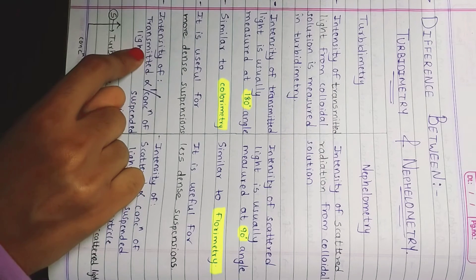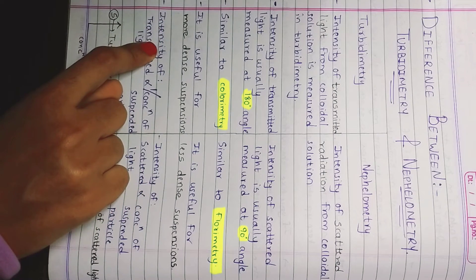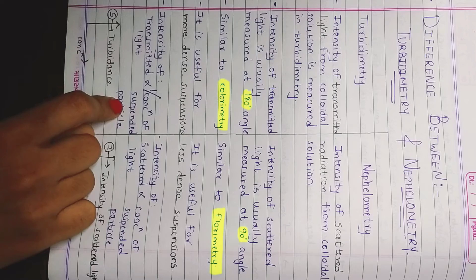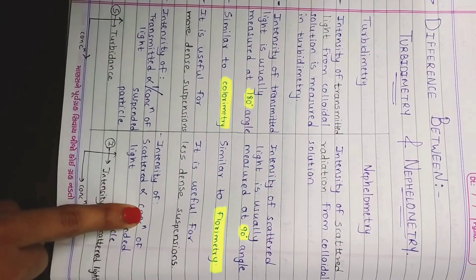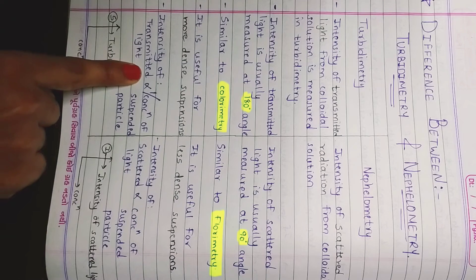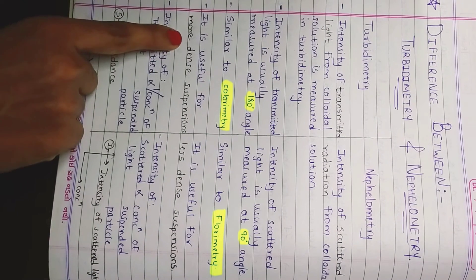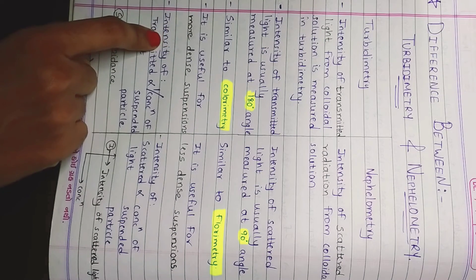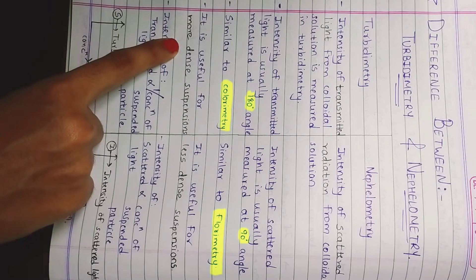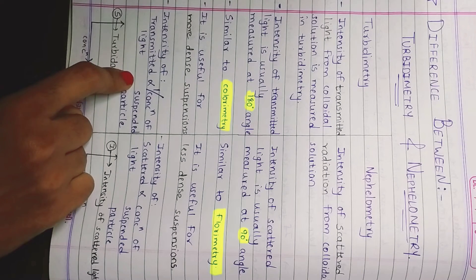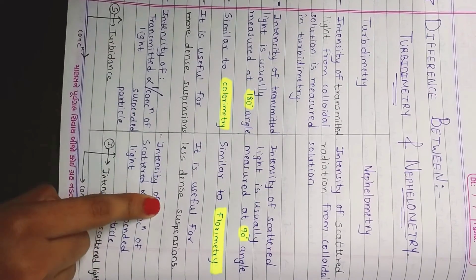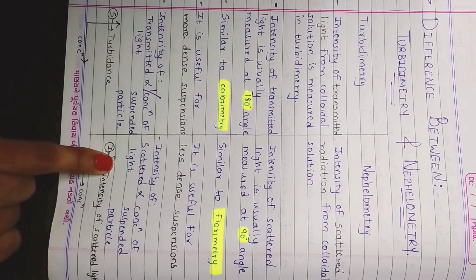Next, the intensity of the transmitted light is indirectly proportional to the concentration of the suspended particles, whereas the intensity of the scattered light is directly proportional to the concentration of the suspended particles. This makes sense because the more dense the solution, the less light will be transmitted through it, and vice versa for less dense suspensions. Nephelometry is based on the principle of scattering.